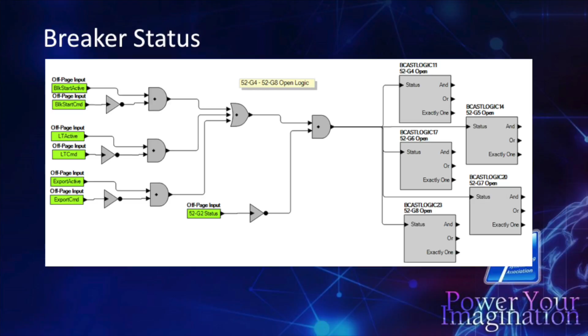And then in our tiebreaker control, and this is the main tiebreaker, this is only part of the logic. I know it looks really complicated, but it's not. But we were able to allow for an 86 input from the relays, so we do have protection. We're using BE111s and SEL 751s to protect the utility side. We make sure that we have all the breaker statuses, and they wanted different statuses in their PLC to know when we were doing certain things. Like if sync went active before the generator shut down, or after the generator shut down, they were getting an 81 trip. So I had to put some logic in to prevent that.